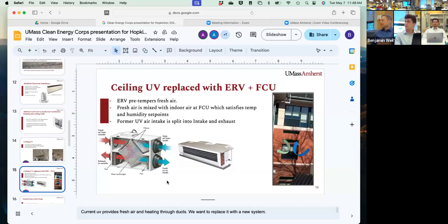Now you're getting the savings that you want. You allow the sizing of both that heating and cooling coil to be smaller because you're not delivering to it humid hot air or frigid cold air. You're delivering to it air that's already been raised to almost room temperature-ish. So for those ones where there's a ceiling to hide everything and where there's a reason to replace the existing fan coil, we compile these as a unit for replacement. And the benefit there is you can remove the exhaust air from that classroom because it's happening through the existing unit ventilator air intake. You're splitting that intake into intake and exhaust.